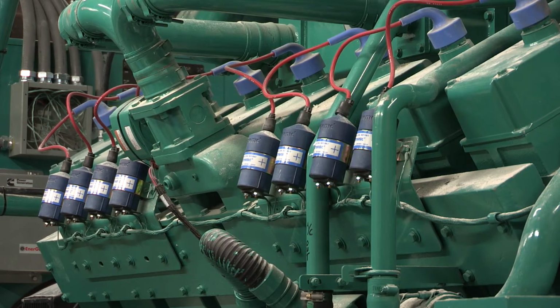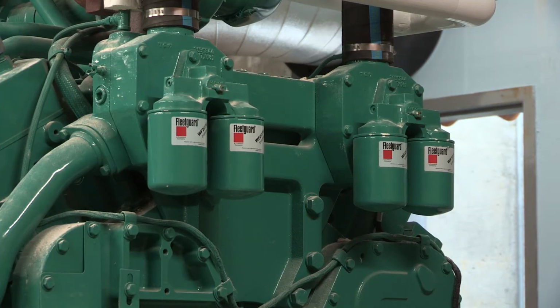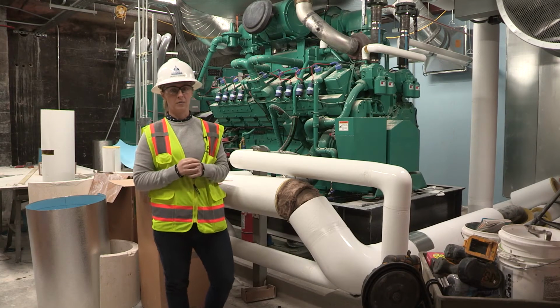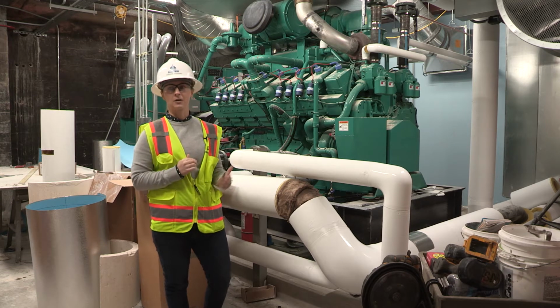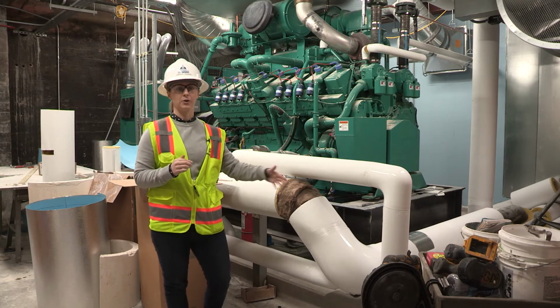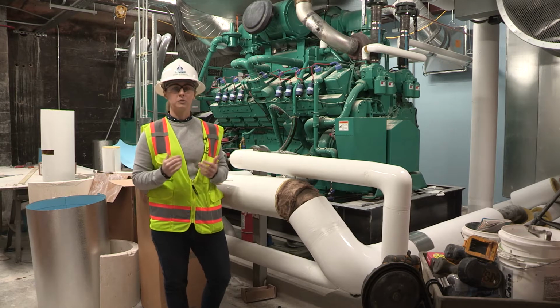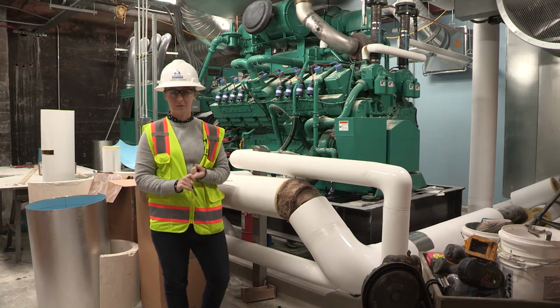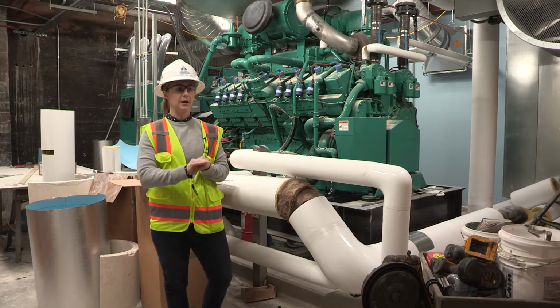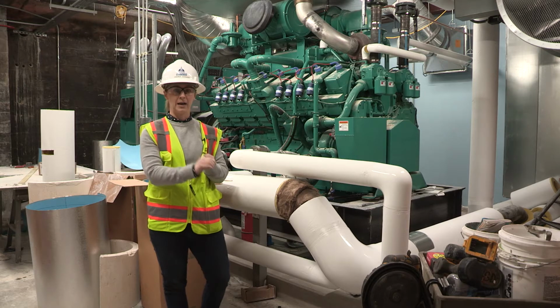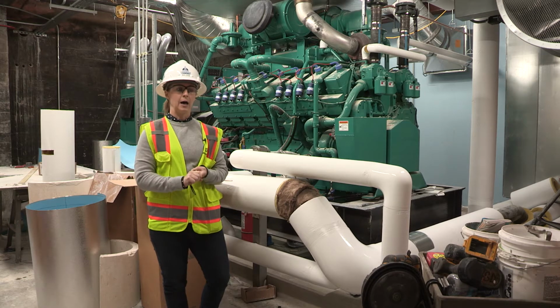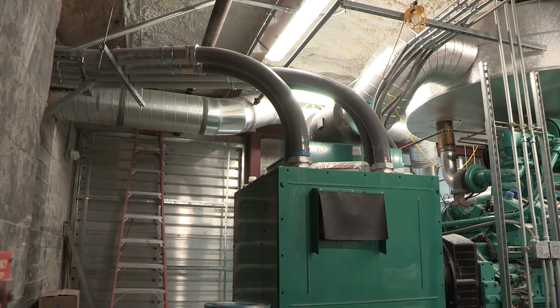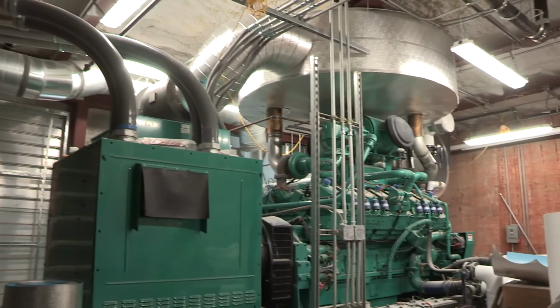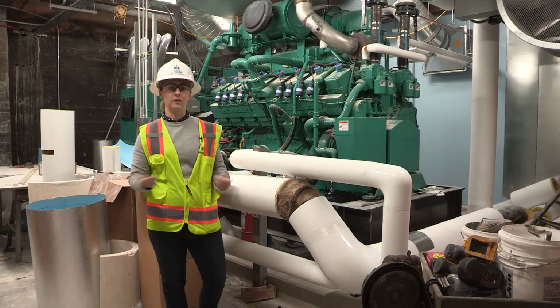As new electrical services are transferred in the building, they'll be backed up by this emergency generator. The emergency generator provides power to the emergency services in the building. It won't necessarily keep your office at 75 degrees or run your computer and lamp, but it will power emergency services such as the fire alarm system, security systems, and the life safety system, allowing lighting for a safe path of egress. It'll also furnish power to all the major IT rooms, and it systematically lowers elevators so passengers don't get stuck during a major power outage.